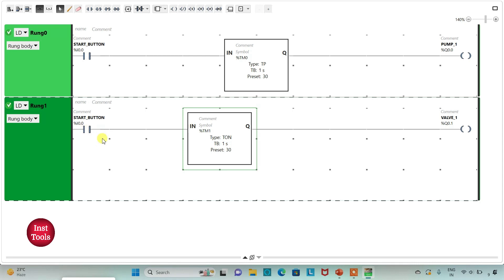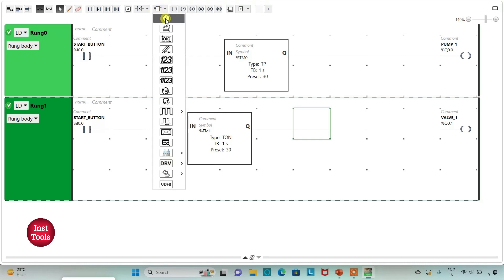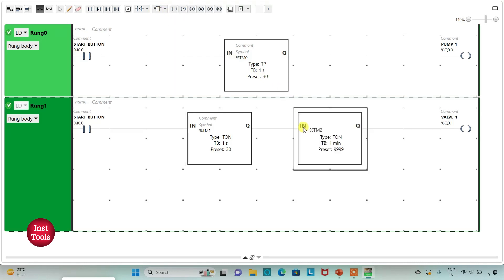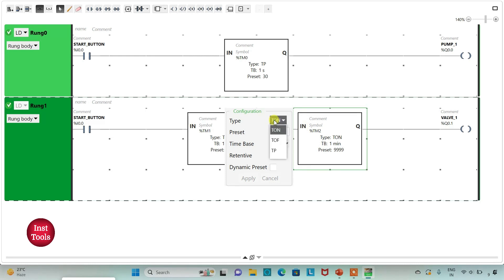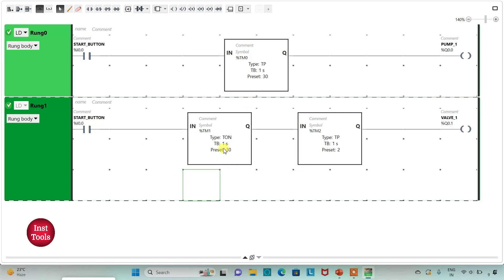When the start button is pressed, Valve 1 will turn on after 30 seconds. It should be activated for 2 seconds only, so for that I will use another timer — a pulse timer TP. I will insert a TP timer, change the time base to 1 second and preset value to 2, then click Apply. So after 30 seconds Valve 1 will turn on and be activated for only 2 seconds.